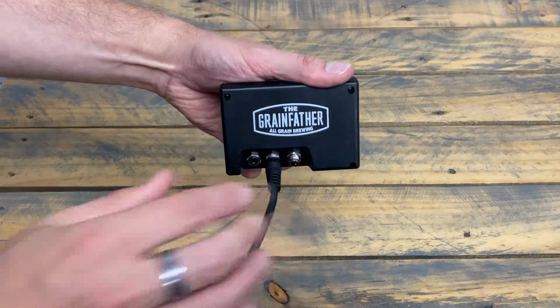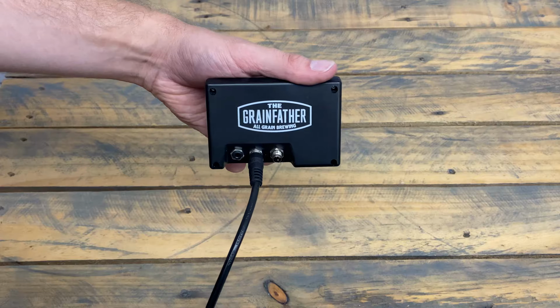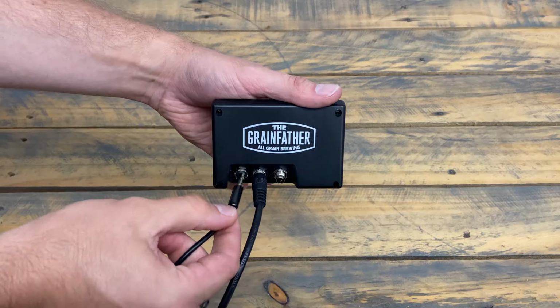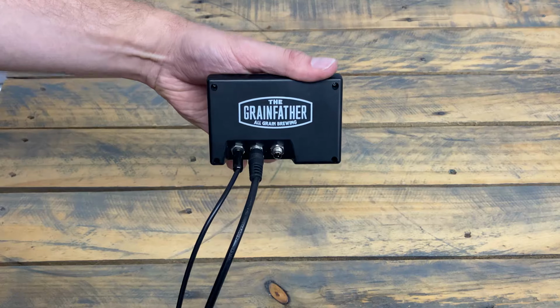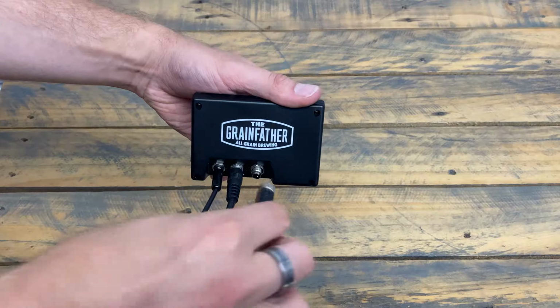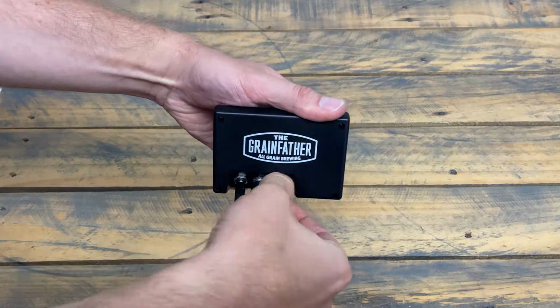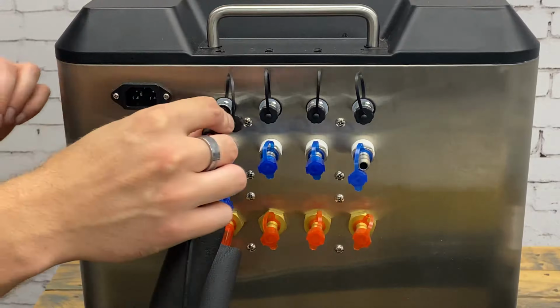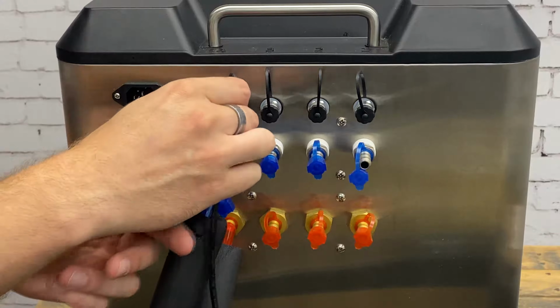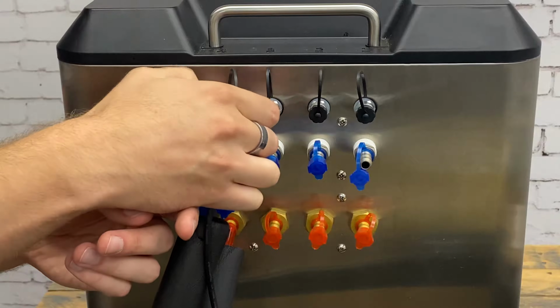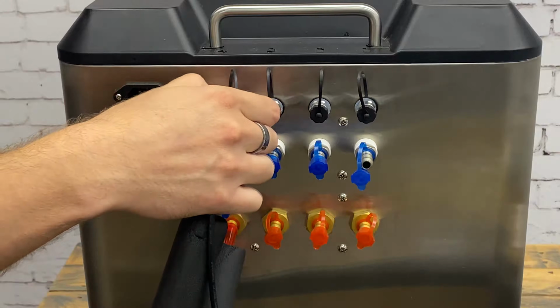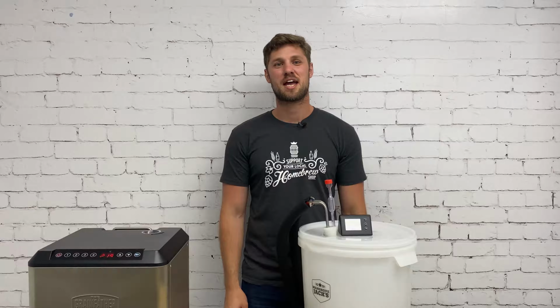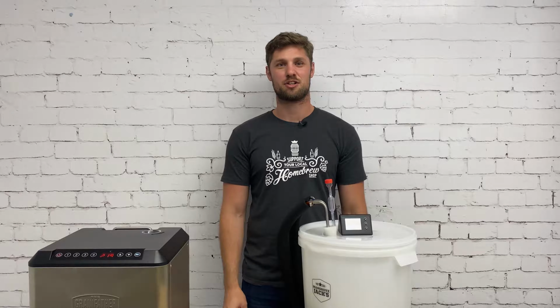Connect the heating pad to the middle socket of your GCA controller. Then attach the temperature probe to the left socket and connect the glycol chiller to the right. Finally, take the other end of the power cord and connect it to the channel on the glycol chiller. And now your GCA is ready for controlled fermentation.